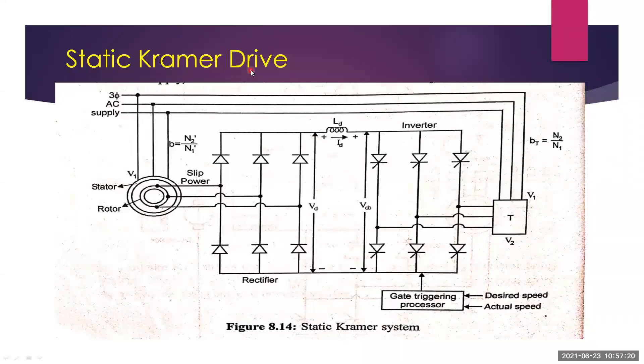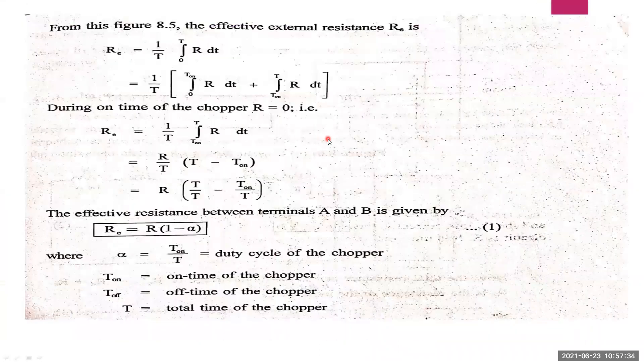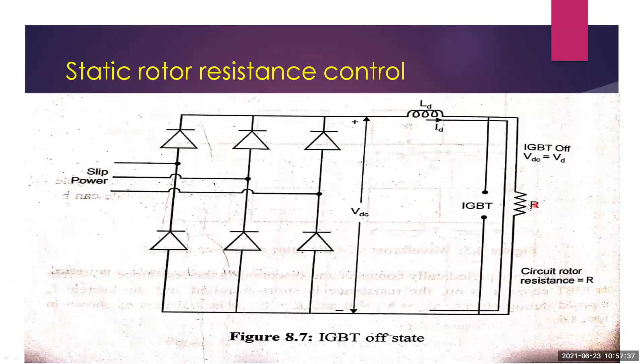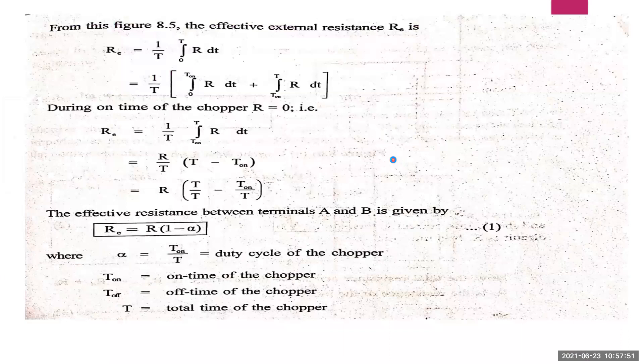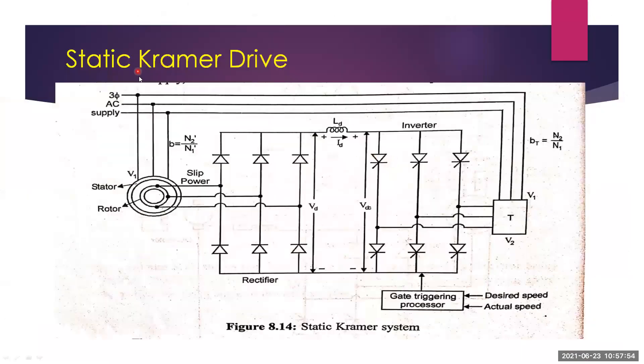This is the static Kramer drive system. In the rotor resistance control method, the slip power is wasted in the rotor circuit resistance. This is why that method is an inefficient method. To overcome the drawbacks of the static rotor resistance control method, the static Kramer drive is used.